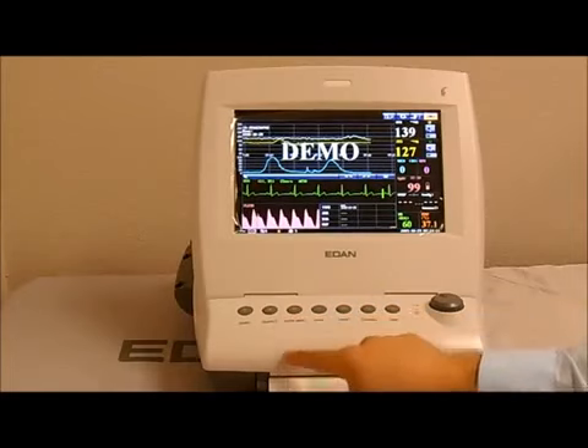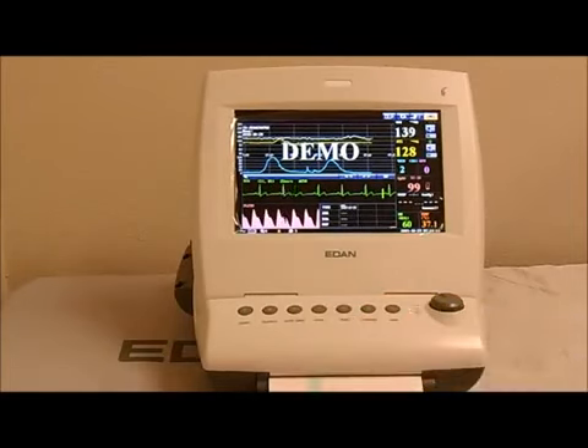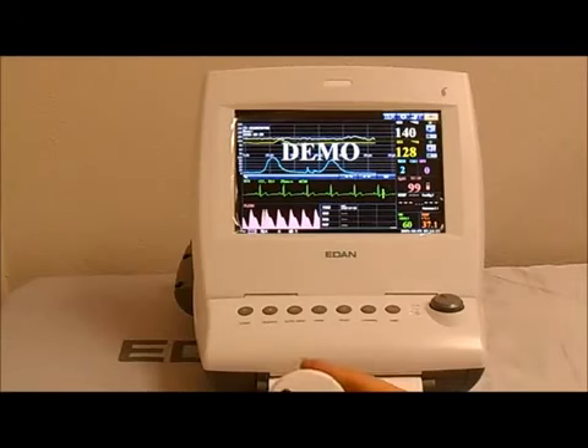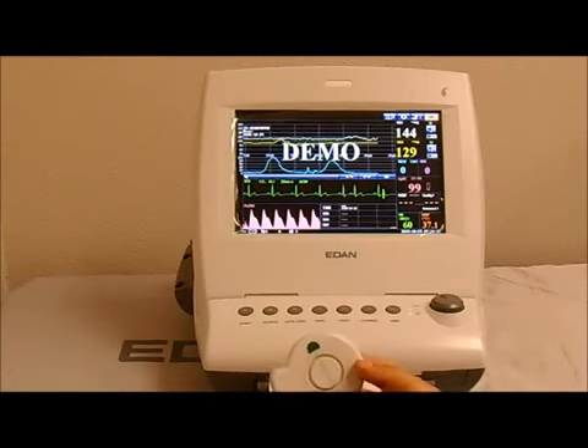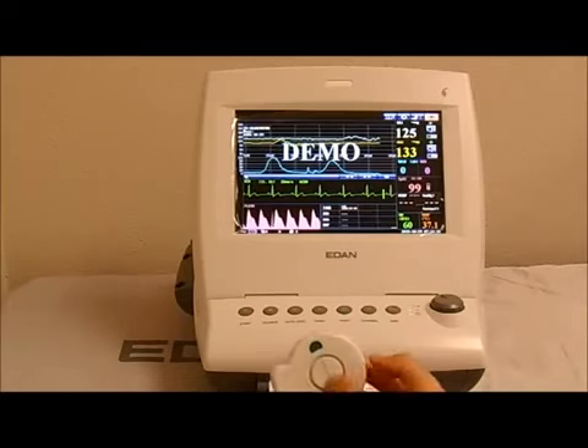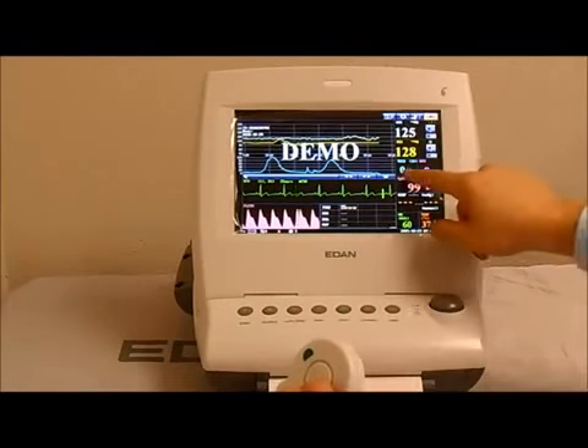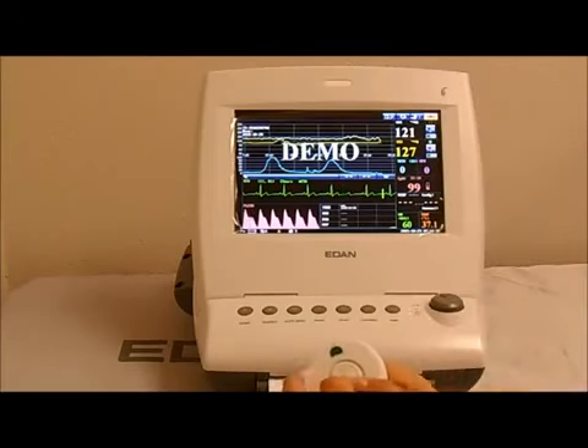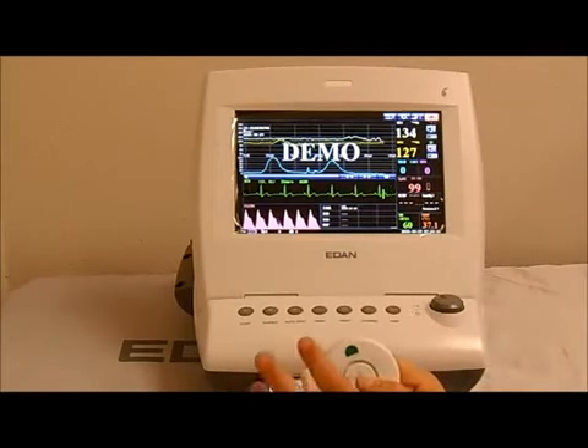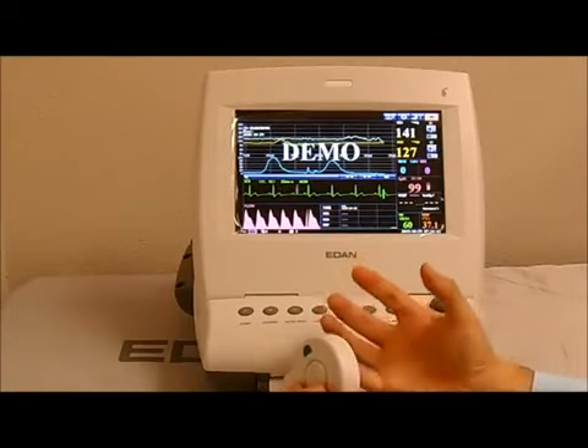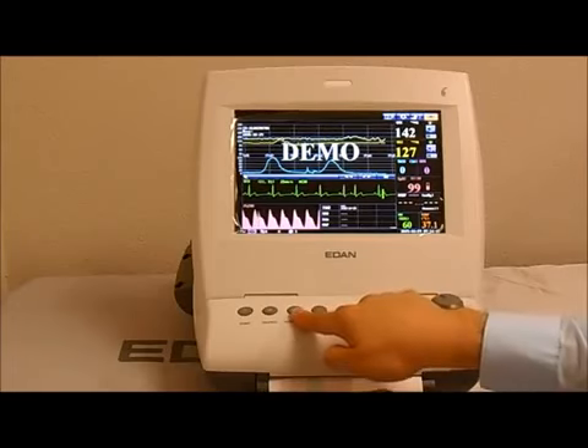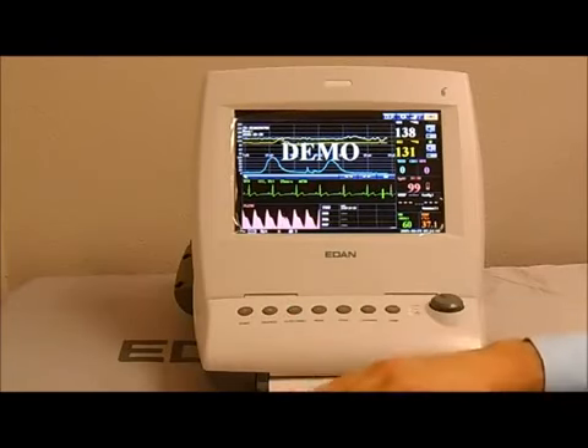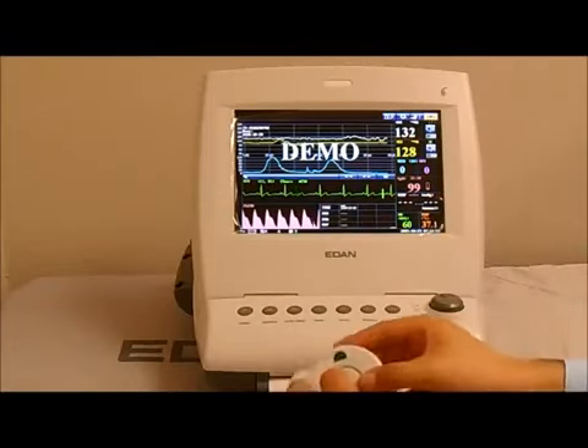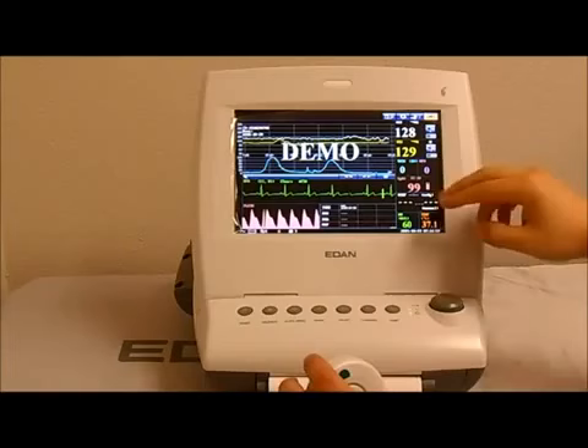Next we have the auto zero. The TOCO transducer, which I have here, is a pressure transducer. So when you place it on the patient, just due to the nature that you're going to be putting a belt on it, there's going to be some excess force. When you first place it, the monitor will give you a TOCO reading, just due to the pressure from the belt. In order to take it back to baseline, you press the auto zero. It'll take it back to the baseline, and only if there's additional pressure as a result of a contraction will the TOCO measurement reading go up.